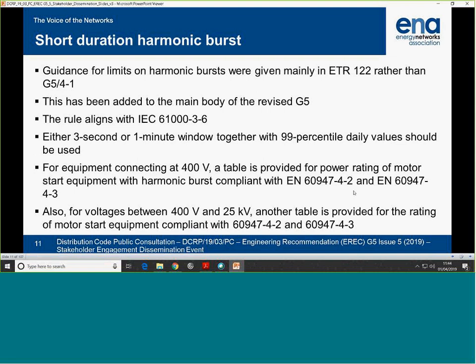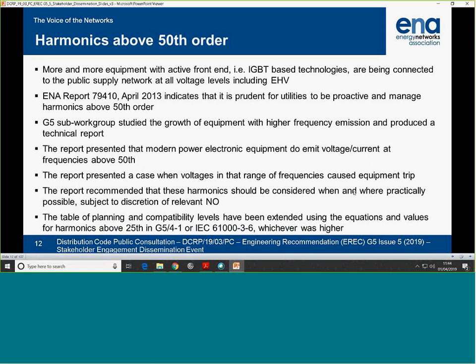Now, I don't want to get detailed because of time, but in Q&A, obviously this means you need to have different equipment to do this and all that. But we are limited in time for harmonics. The sub-working group came up with a very, really good report. They assessed all equipment, they assessed actual measurements, and the information on whether these caused any problem in the field. Yes, there are cases where harmonics above 50 actually caused PV to trip in UK. It's a very good report, and I think because it's part of the working group, it's public.